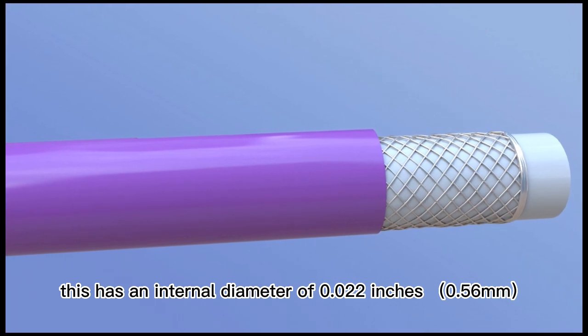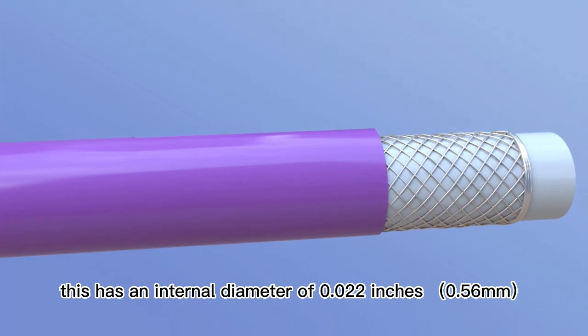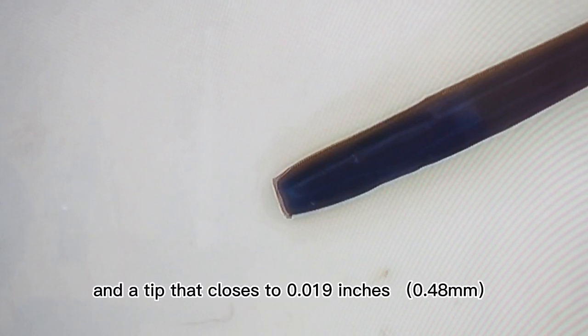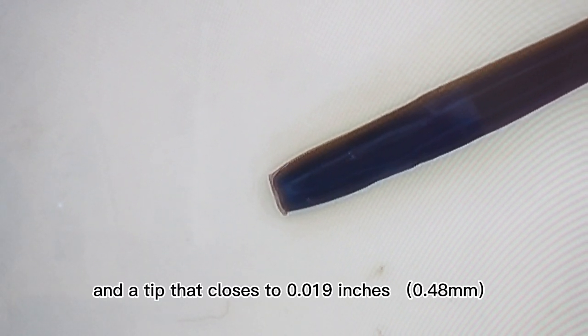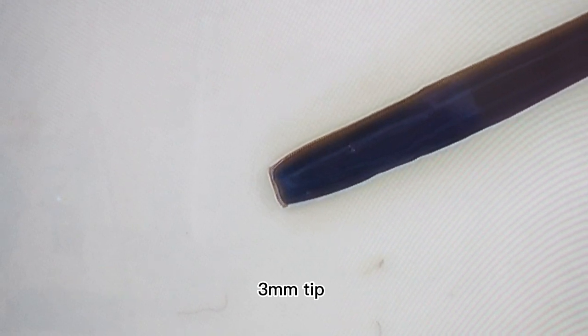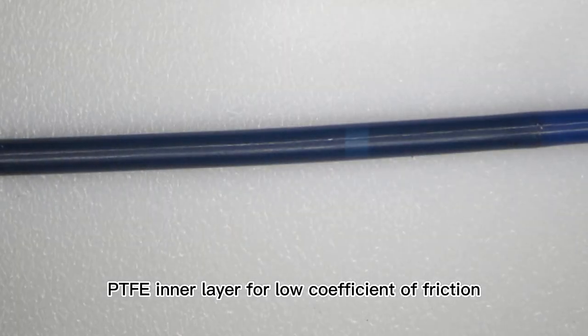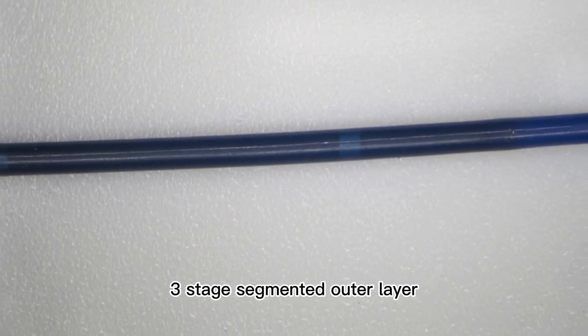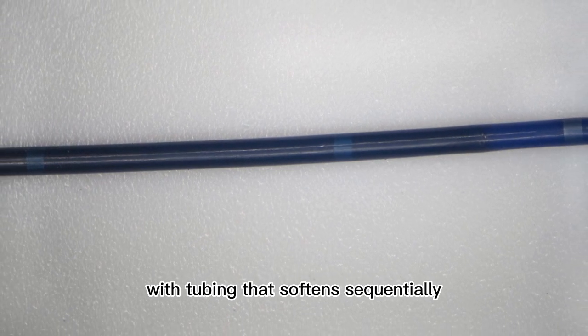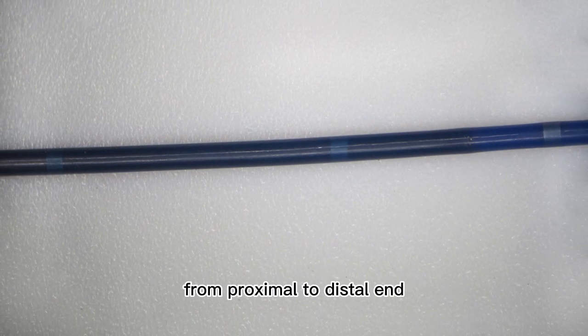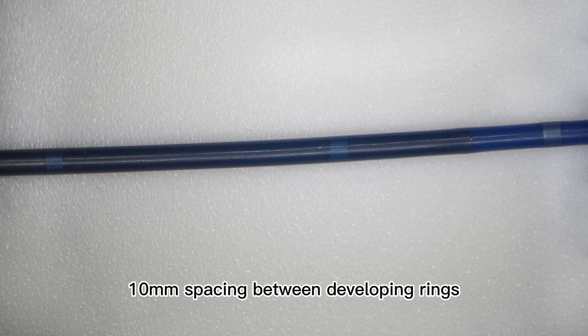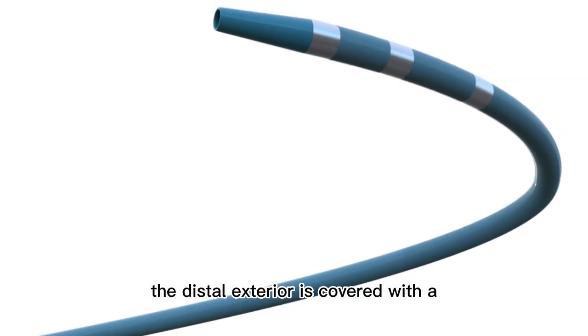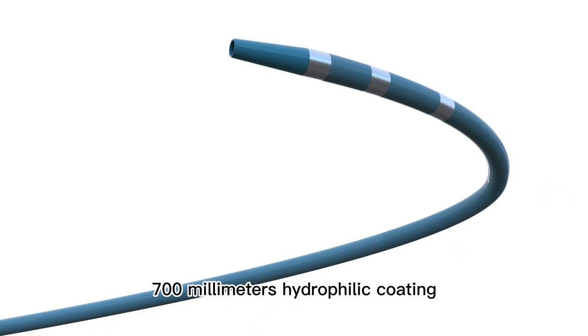This has an internal diameter of 0.022 inches, 0.56 millimeters, and a tip that closes to 0.019 inches, 0.48 millimeters. 3 millimeters tip, ETFE inner layer for low coefficient of friction, 3-stage segmented outer layer with tubing that softens sequentially from proximal to distal end. 3 developing rings, 10 millimeters spacing between developing rings. The distal exterior is covered with a 700 millimeters hydrophilic coating to reduce friction with the vessel.